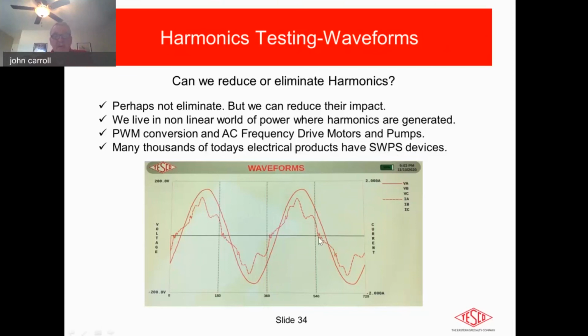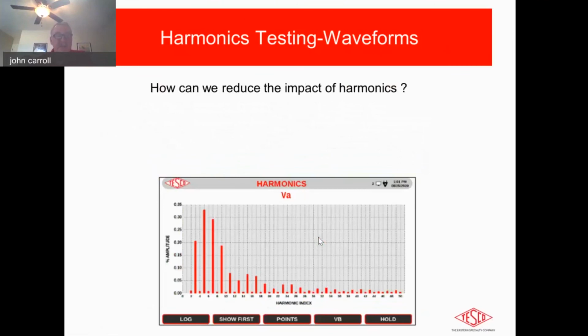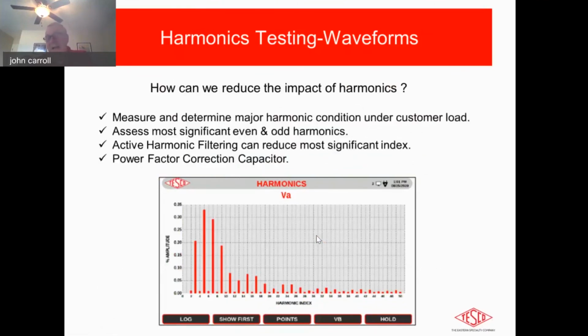So, without going into any more detail on that, these are just some of the impact conditions. How can we reduce them? Well, rather than eliminate them, like we said, you can measure and determine what they are. You can assess the most significant. There's a lot of great products out there that do active filtering that will reduce the most significant. That could drop the problem down by 50% right there. And many customers out there, as you're probably aware, will do power factor correction capacitors. That's also fairly common. Be aware, though, that they do switch as well. So it's a bit of a balance between them all.